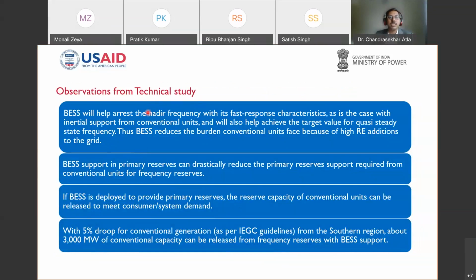This is very critical for any system when renewables are being added into the system, because as inertia is going out for the future. And with its fast response, BESS, taking advantage of the power electronics, helps to support fast arresting of the nadir frequency, and also helps to get to your quasi steady state. In addition to that, even 1 hour of storage capacity for this 1100 range of BESS is sufficient to handle all the RE variations which occur on a daily basis.